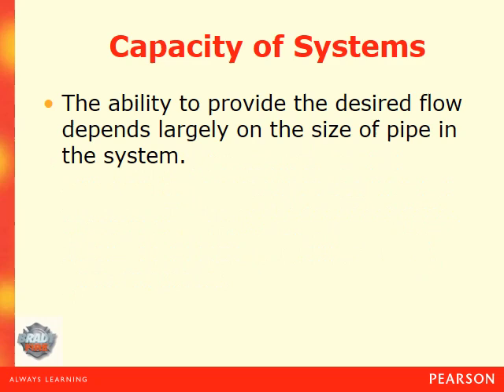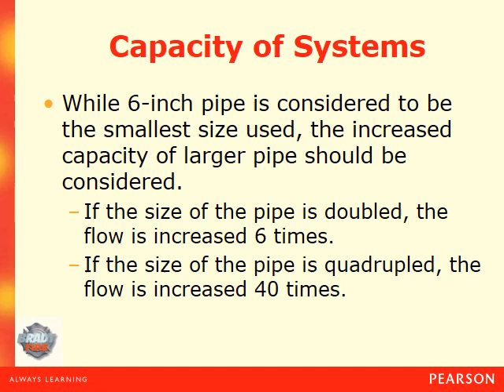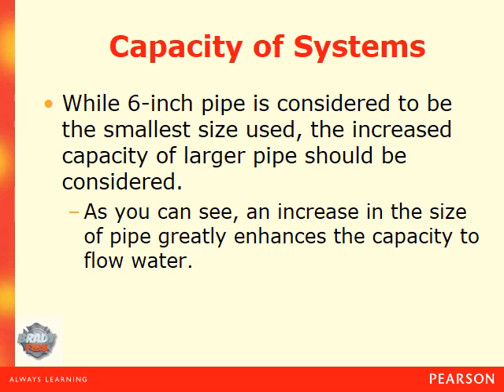The ability to provide the desired flow depends largely on the size of the pipes within the system — the larger the pipes, the more gallons per minute you can get. While six-inch pipe is considered the smallest size used, the increased capacity of larger pipes should be considered. If the size of the pipe is doubled, the flow is increased six times. If the size of the pipe is quadrupled, the flow increases 40 times. An increase in the size of the pipe greatly enhances the capacity to flow water.